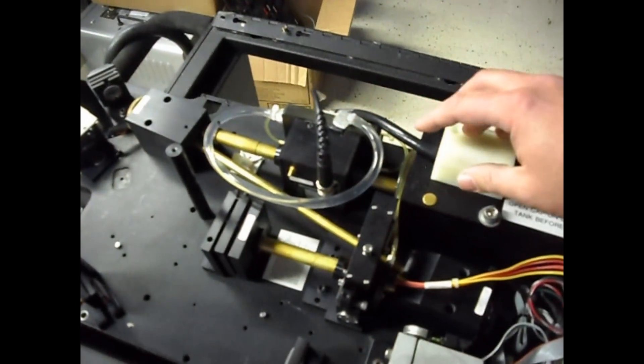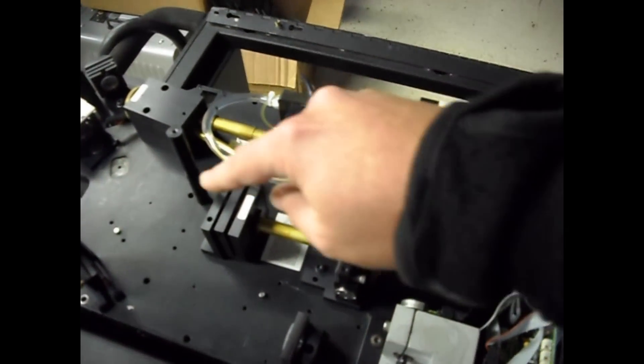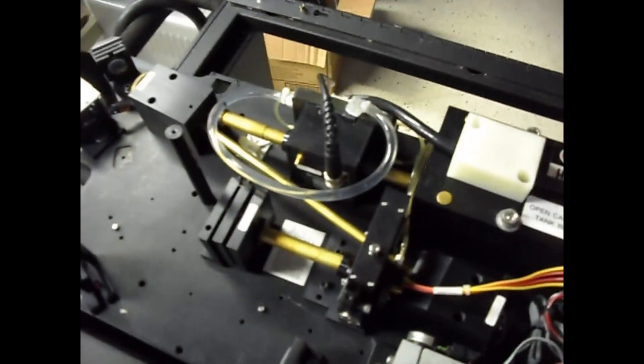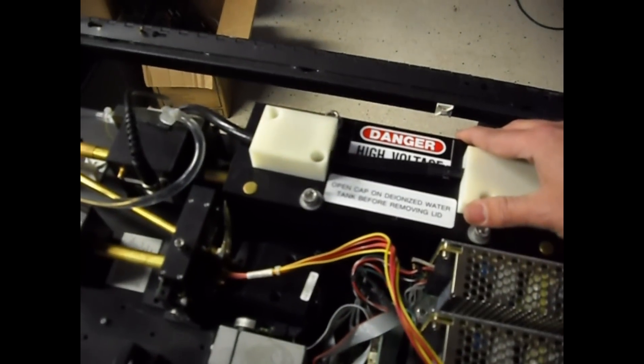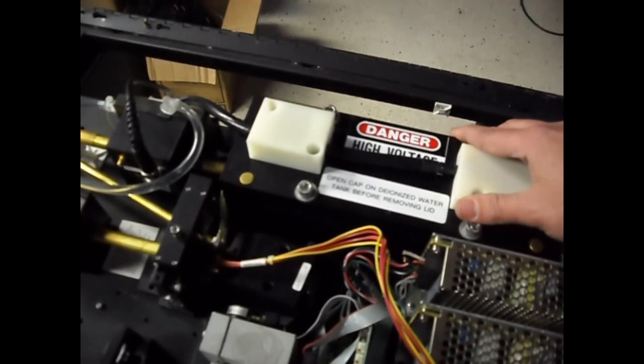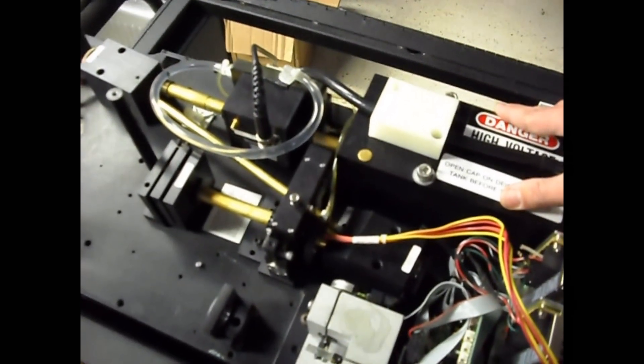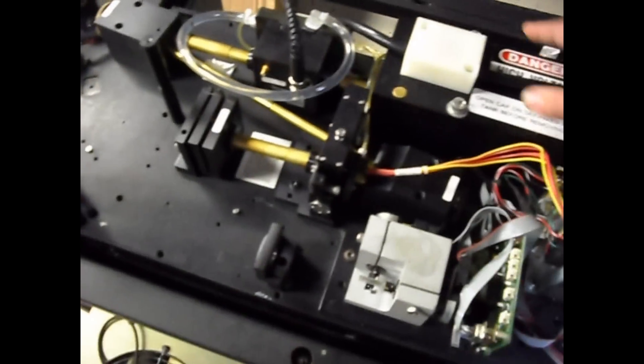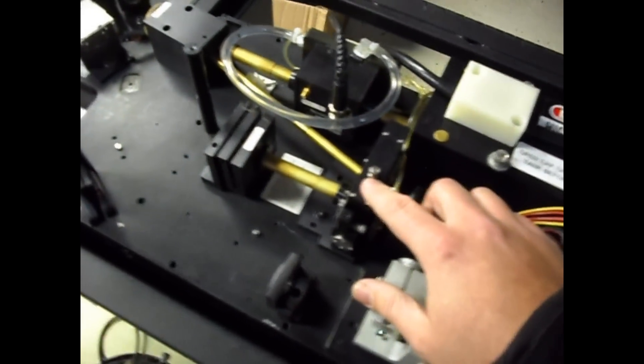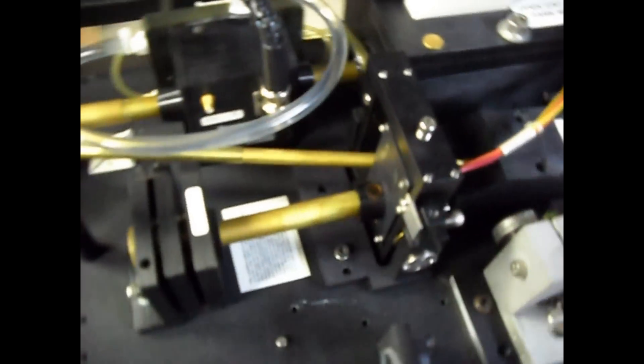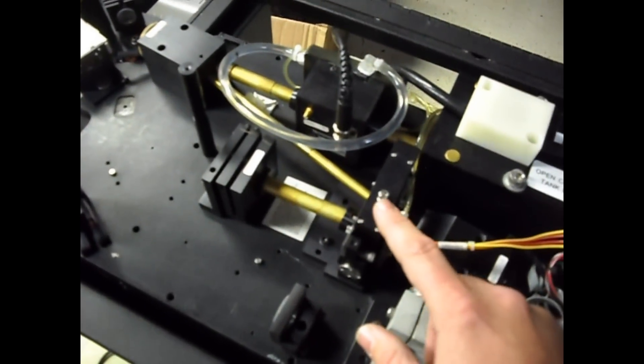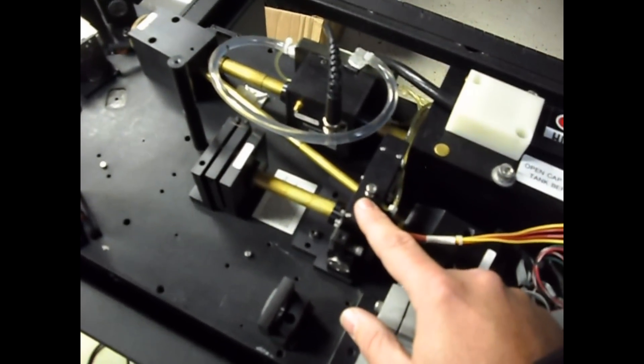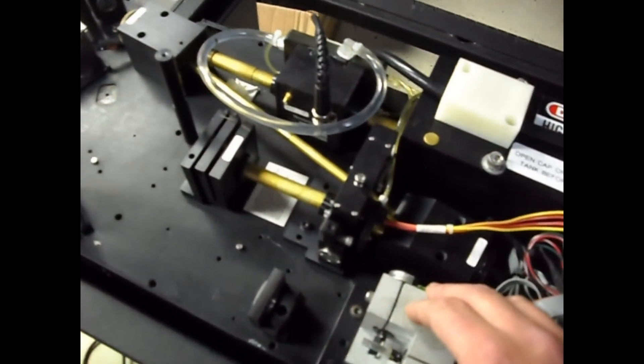From there we can see the rest of the components. Right here, this is called a Z fold cavity. As you can see, it has this kind of Z shape to the optical train for the frequency doubling portion of the laser. Because the YAG rod basically creates 1064 nanometers of infrared light. From there, the infrared laser beam is frequency doubled using the KTP crystal which is located in this housing right here, along with the KTP heater. Essentially what it does is it cuts the wavelength of the light in half, turning it into 532 nanometers of light, which is green in color.